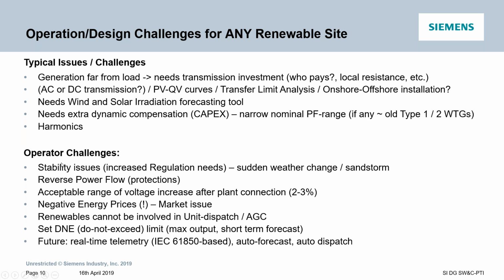From an operational point of view, we have stability issues in the network, and we could have reverse power flow. If a network has a significant amount of rooftop PV installed in a specific area, on a sunny day the loads can become power producers instead of consumers, and power can start flowing from the low voltage network upwards to the transmission network.